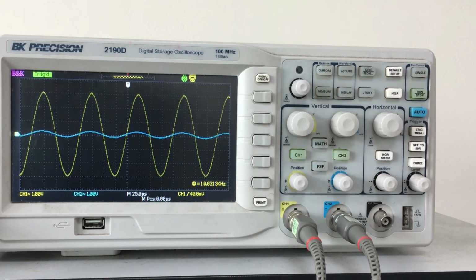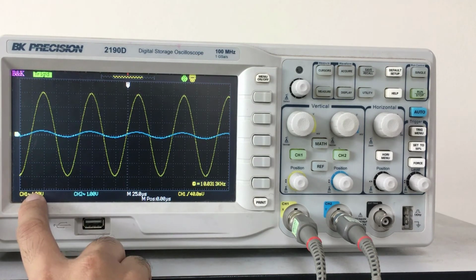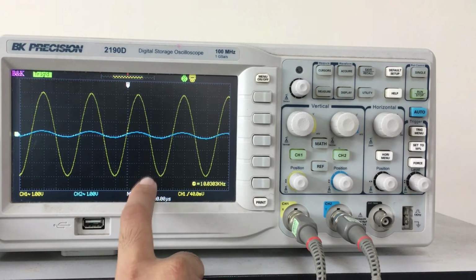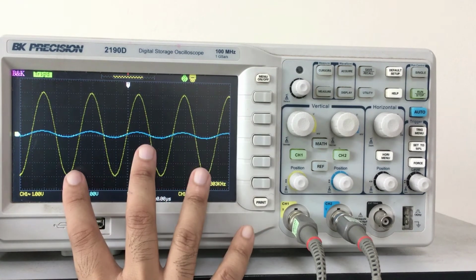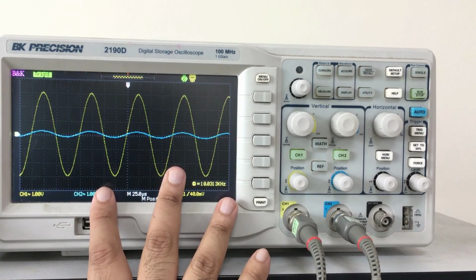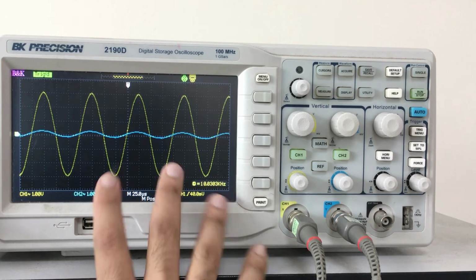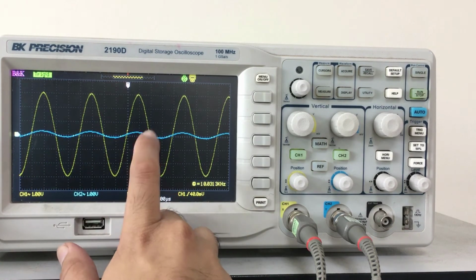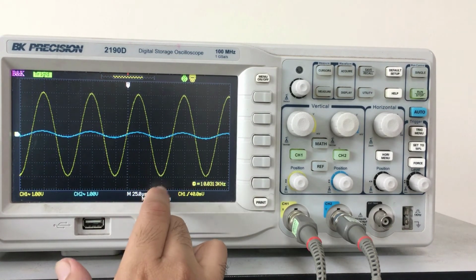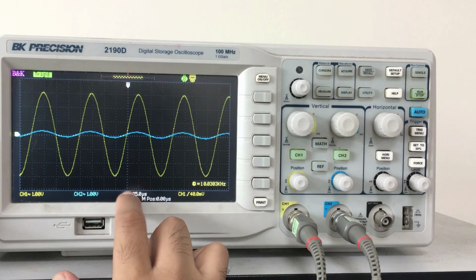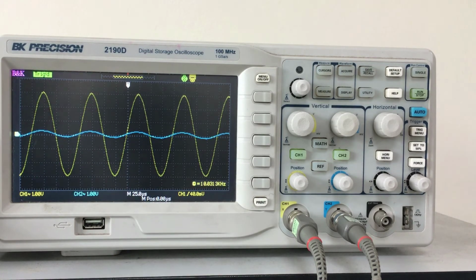The important thing is that once we store the waveform, we can no longer edit it when we recall it. So whatever settings you have for channel 1 and the time settings here will be the version of the waveform stored in reference. It's important to keep the time base the same when making measurements, otherwise you will not get an accurate phase calculation.